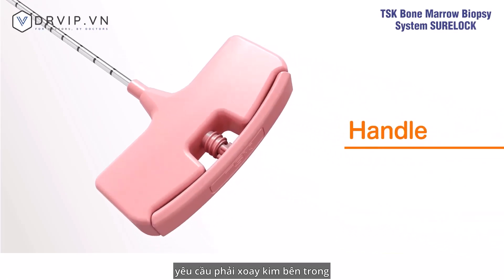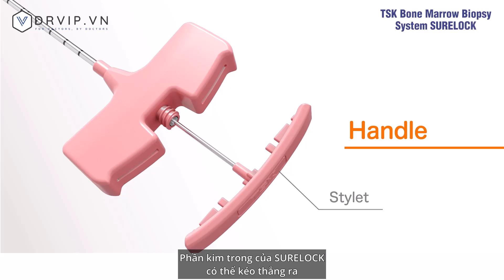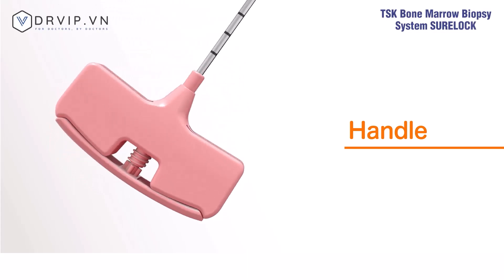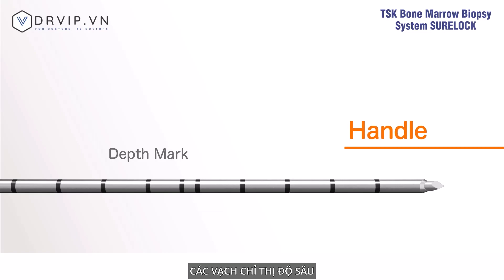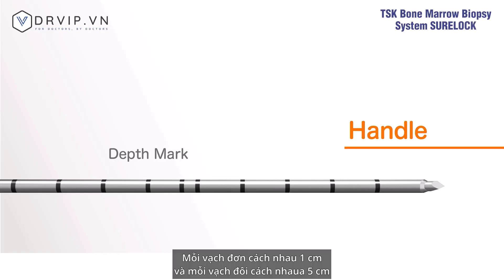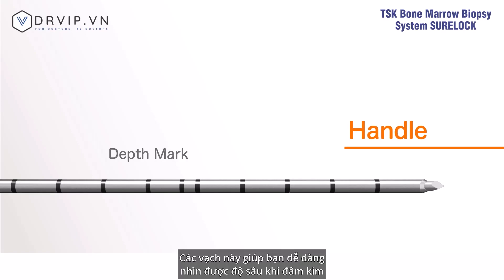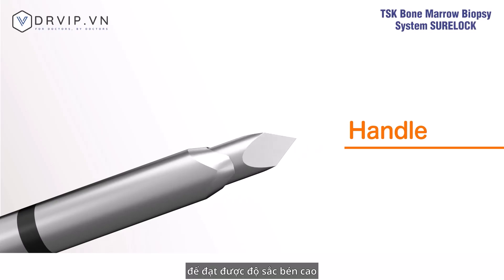Unlike locking type bone marrow biopsy needles that require rotation of the inner needle for removal, the SURELOCK has a stylet designed to be pulled straight out. The depth marks — single lines at each centimeter and double lines at five centimeters — let you visually check the depth of insertion. The needle tip is processed for excellent sharpness using grinding technology developed over many years.